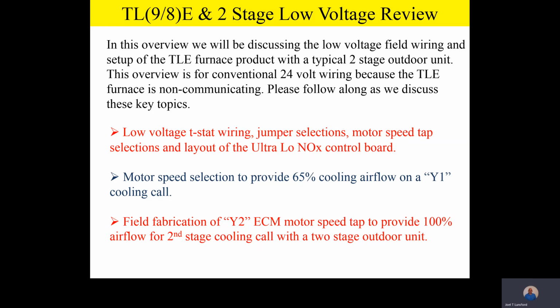Low voltage thermostat wiring, including jumper selection, motor speed tap selections, and layout of the ultra low NOx control board. We're also going to talk about motor speed selections to provide 65% cooling airflow on a Y1 call, and then a field fabrication of a Y2 ECM motor tap to provide 100% airflow for a two-stage cooling call with a two-stage outdoor unit.